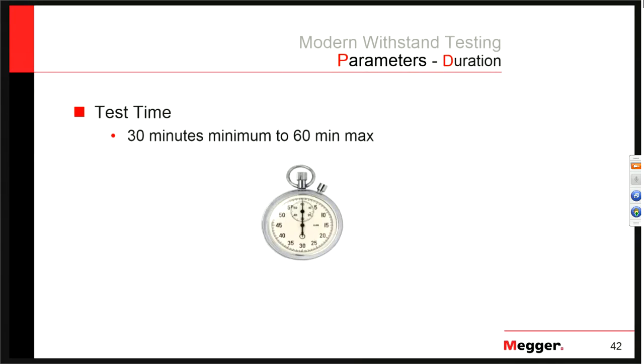Q&A: At what cable age should we start implementing VLF testing? Some standards recognize DC testing up until about 5 years of the cable's life. However, you can use VLF the entire life of the cable — there's no equivalent age limit compared to the 5-year limit on DC testing. If you're asking when you transition from acceptance test values to maintenance test values: you do the acceptance test, put the cable in service, and then after about 3 to 5 years you start looking at maintenance test values exclusively.